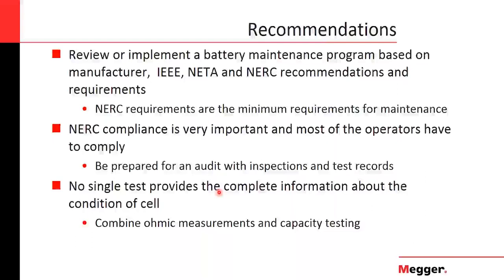So a combination of tests is the best way to determine the condition of the battery, and combining these two types of tests, the ohmic measurements and the capacity testing, will give you a very good indication of the condition of the battery. Of course, we have equipment that can perform all of these tests. As I was mentioning, an impedance tester can give you most of these measurements, or the tests that you need to perform. The BITE 2 or BITE 2P can measure the ohmic value, the voltage of each cell, the float voltage, and the current of the entire system, the ripple current, the strap resistances, and you can check battery continuity.